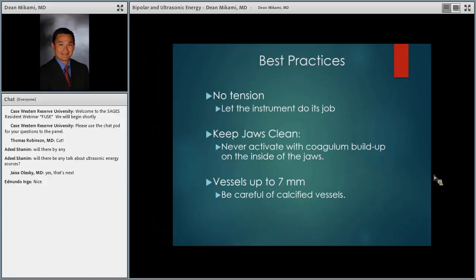So best practices, you really want coaptation, but you don't want to pull up on it too hard. You want the bipolar energy device to do its job. You really want to keep the jaws clean, right? Because it's your active and your dispersive electrode in one instrument. You want to make sure that the eschars are wiped off, and you have to be very careful. It can seal up to 7 millimeter vessels, but if you have calcification, that may affect your seal.